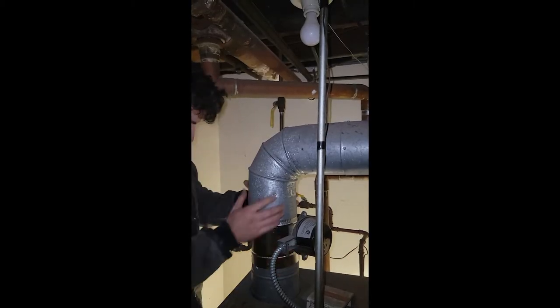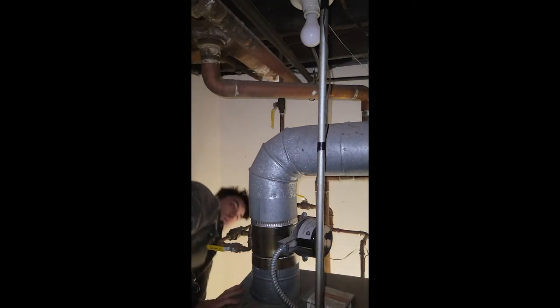There are some leaves and debris in the burner — I wonder if something is being jammed up. You can see how this damper is being jammed right now. Let me put a drop of oil on it. On the other side there's also a seat.